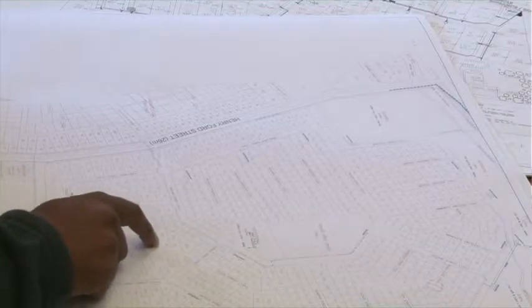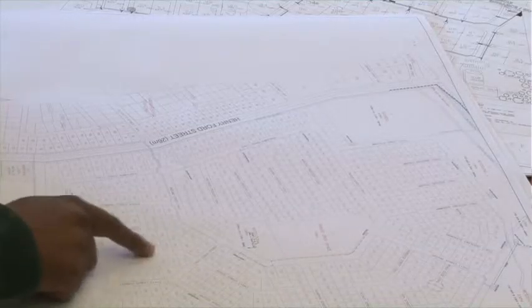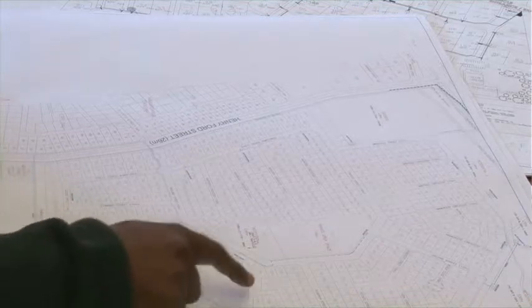Now, herein lies a key element. When you design the township layout, and you're doing your electrical layout, you start off with the medium voltage system. You've got to do an optimum scheme. You can't just go in and say, right, I'm going to put a cable in there and service this stand this way, and that stand that way. There's a lot of thought that goes into this, and it's an iterative process. You'll never get it right the first time.